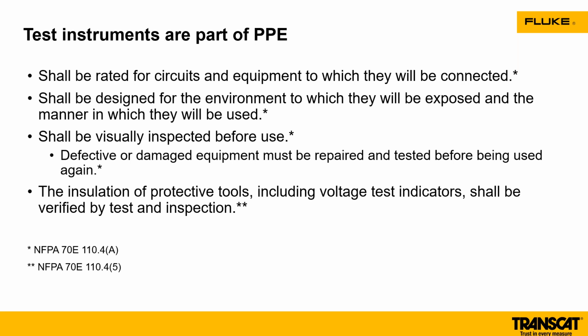Make sure that you don't have defective or damaged equipment or test leads. Again, these are the tools you're using out there doing these jobs. You need a meter to make those measurements, whether it's voltage or current. They need to be in good working order. You don't want to be part of those statistics, just like on slide one, where that arc flash or arc situation happened. So we just want to make sure that our tools are insulated, we're working with the right meter, and that it was tested, and that we verified that it's tested.